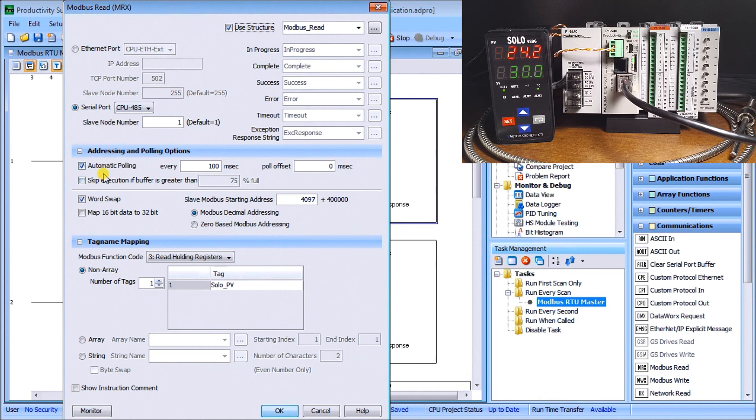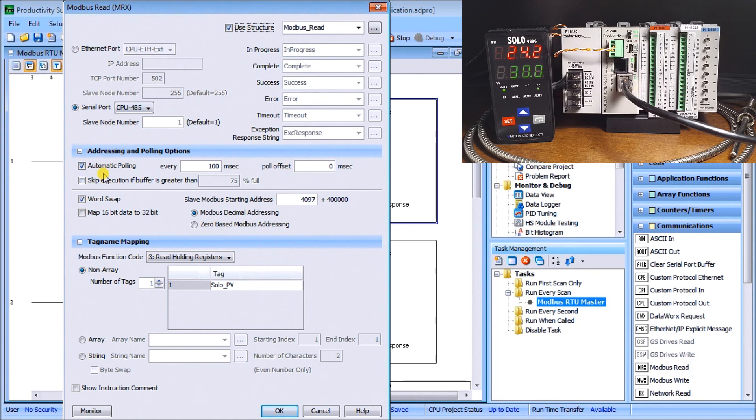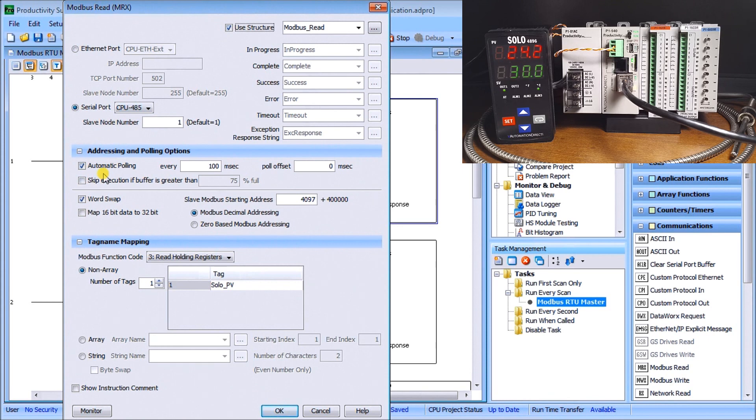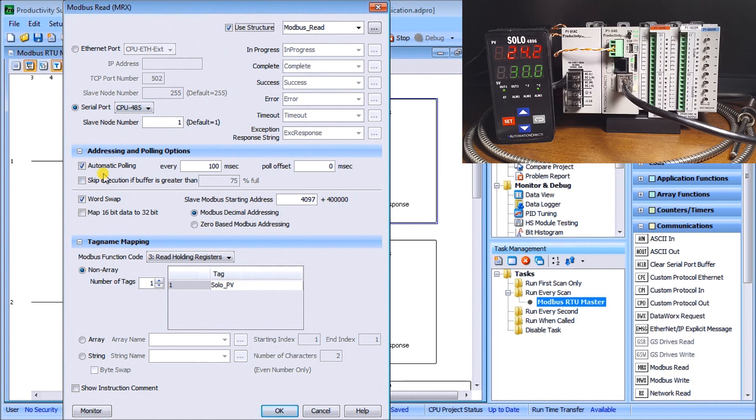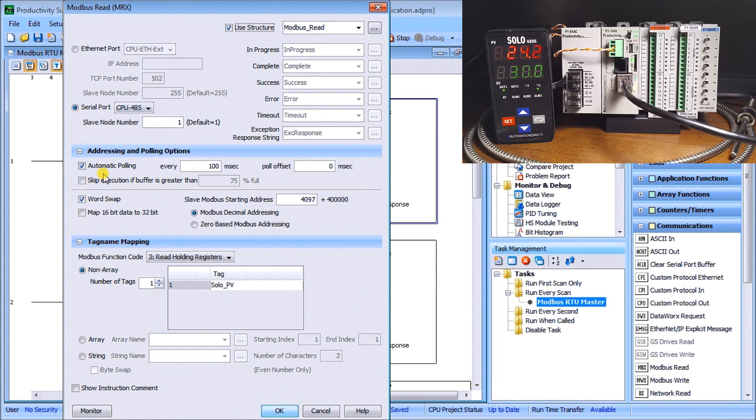One of the most powerful things is our address and polling options. We're going to set this up for automatic polling. What that means is that all of the logic for sequencing for all of our modbus read, modbus write or network read and write is all done through the firmware of this instruction. This is very important and makes programming of the modbus network very easy. We set it for automatic polling every 100 milliseconds, so 10 times a second.